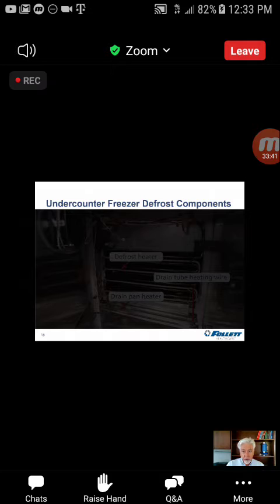I do appreciate that. So next up, this was the under-counter freezer. One other point I'd like to make is you probably noticed that the defrost heater, the high wattage heater on the face of that evaporator, is directly behind that rear panel. Now that panel does a pretty good job of isolating the defrost heat away from the product, provided the product is not shoved up against the wall. So on a freezer, it's important to make sure that the staff is not doing that, because it will pick up some of the heat from that defrost heater during the defrost cycle. We need to leave a little gap there, okay? If it's pushed up against the wall, then it's going to pick up some of that heat when the unit goes into defrost. So that's the under counter.